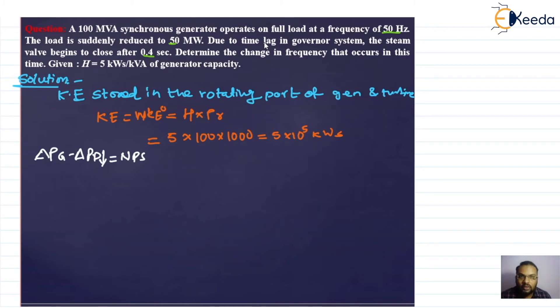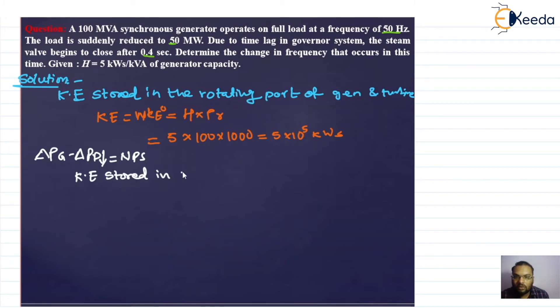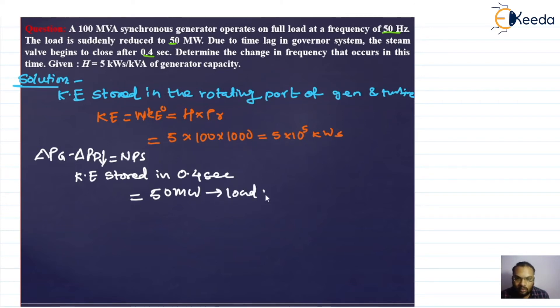The gate closing operation begins after 0.4 seconds, so after that point we no longer have net surplus power. We get that net surplus power only for 0.4 seconds. Therefore, we calculate the amount of kinetic energy stored during that 0.4 second window. The load reduction is 50 MW.